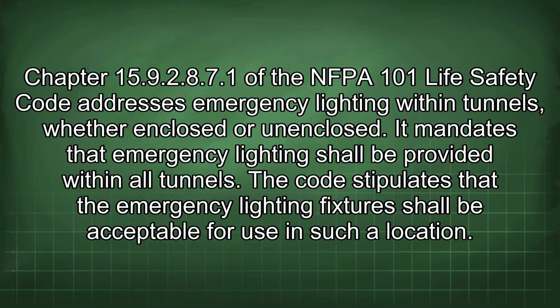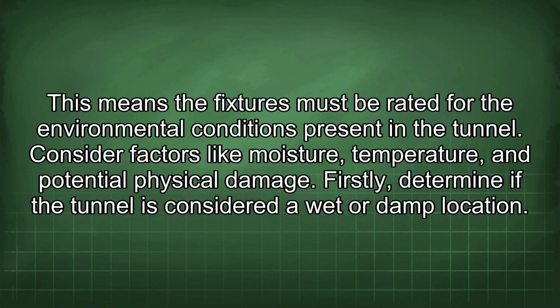Chapter 15.9.2.8.7.1 of the NFPA 101 Life Safety Code addresses emergency lighting within tunnels, whether enclosed or unenclosed. It mandates that emergency lighting shall be provided within all tunnels. The code stipulates that the emergency lighting fixture shall be acceptable for use in such a location. This means the fixtures must be rated for the environmental conditions present in the tunnel.